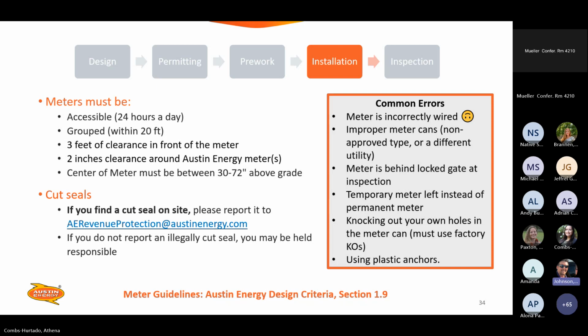So common errors, meter is incorrectly wired. With us not doing net metering, and we have 2 meters, we have the revenue meter and the PV meter. The revenue meter must be wired with the grid power on the line side, so everything can be read properly for billing purposes. On the PV meter, the PV, the solar, is the source circuit for that meter. And because we have the benefit of solar buyback program, it must be on the line side of the PV meter so that it can be read properly.